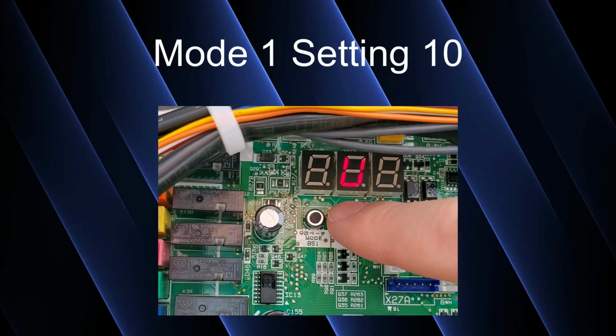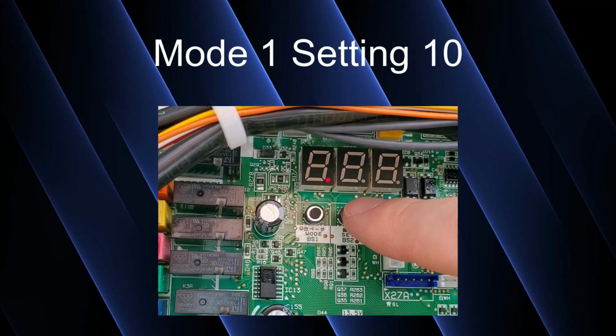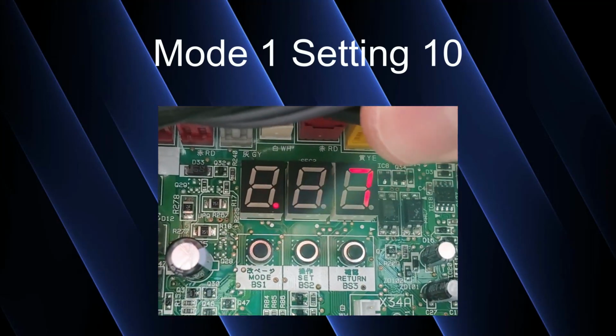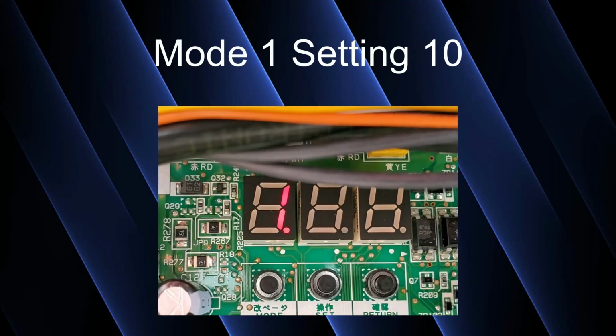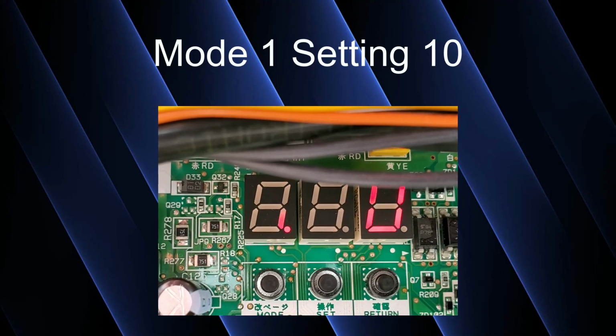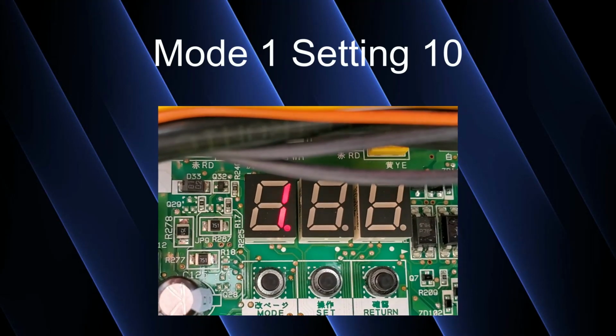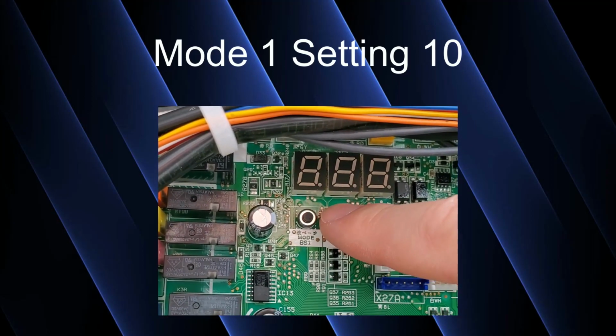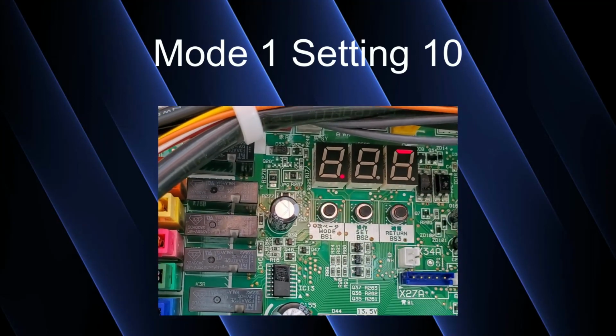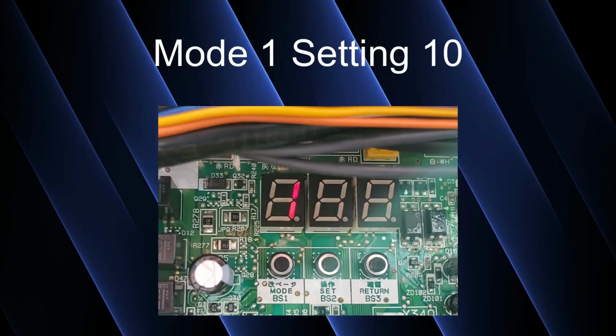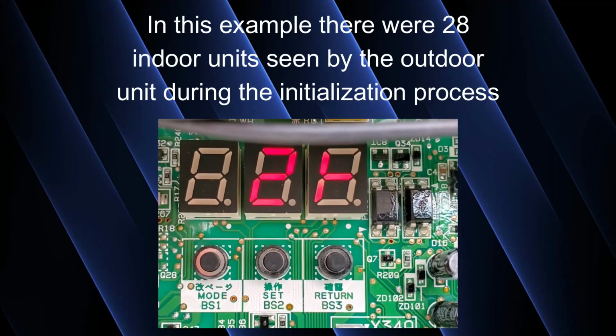So just like before, you press the mode button 1 time, but this time the screen displays 1.00. Then you're going to press the set button 10 times. It's very easy to see how many times you've pressed the set button because it shows you on screen every time you press it. 1.01, 1.02, 1.03, 1.04, and when you get to 10, the screen will say 1.10. Then you simply press the return button 1 time and it will display the number of indoor units that it has addressed. And hopefully, again, if you installed 7, you see a 7 shown on screen.